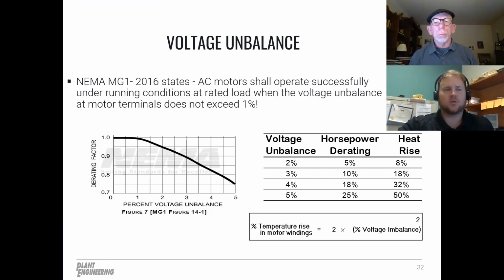So you see a chart on the slide. This is from NEMA's Motors and Generators, MG 1. I call it the Motor Bible, a respected publication in the industry. They refresh it every couple of years. This shows that even voltage imbalance exceeding only 1% leads to derating and excessive heat.